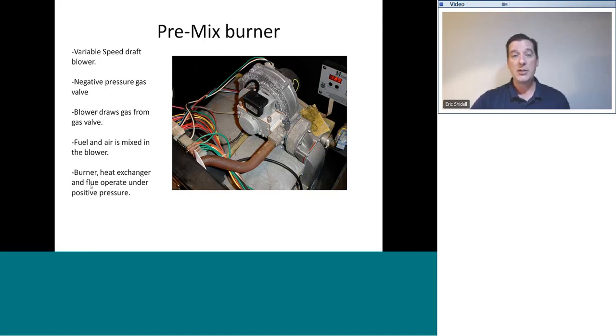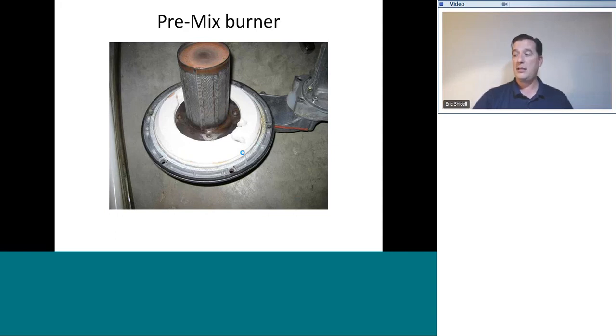It looks like a little power burner. It's absolutely backwards compared. Here's the burner. This is what's on the other end of that blower, what's blowing into. That chain came this way, and this burner's then actually removed and rotated 90 degrees, so it's pointing up. This burner normally points horizontally, and the flames exist 360 degrees around the burner. So that fuel-air mixture is blown into the burner like this, and it leaves the burner 360 degrees all the way around. Pretty neat stuff.